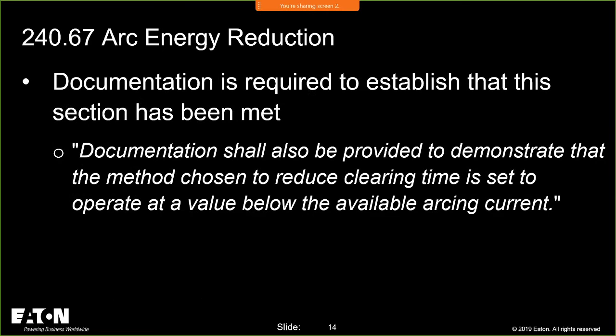Now you need documentation. This is one of the changes that was made, and they made this change to 240.67 and 240.87. Whenever you pick an arc reduction method or technology, you have to provide documentation that demonstrates that it will operate at that arcing current. So that's an important piece of the pie that you need to show. You just don't blindly apply an arc reduction technology. You have to show that it'll actually do something for you. And I think that's critical.